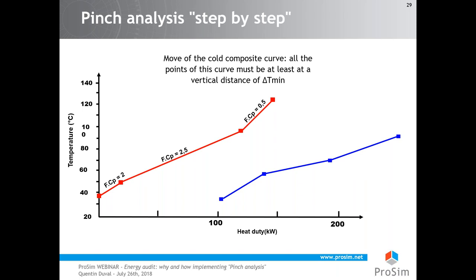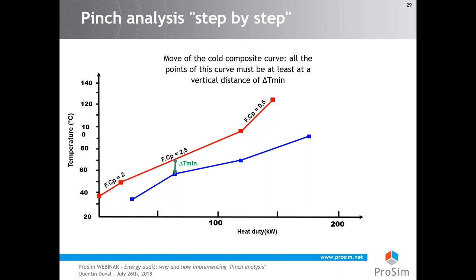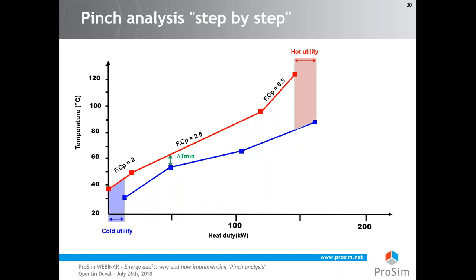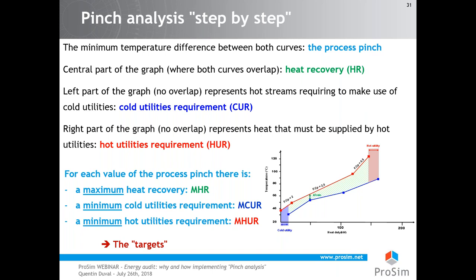As done previously with two streams, we move the cold composite curve below the hot composite curve. When the vertical distance — the pinch — between the curves reaches the target value, we stop moving. With this graphical method we can directly read the minimum quantity of cold and hot utility requirements and, more importantly, the potential heat recovery within the process — the green area. We sum up the results: the method gives the minimum cold utility requirement, the minimum hot utility requirement, and the maximum heat recovery. The next question is how to choose the value of the pinch.